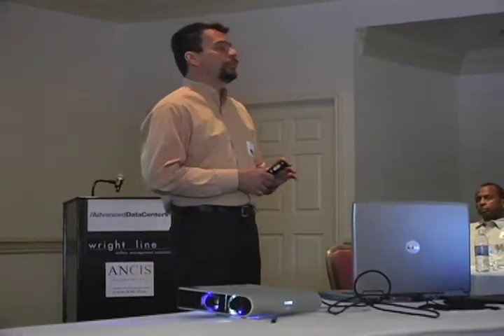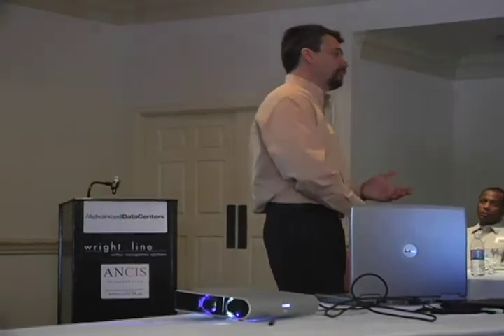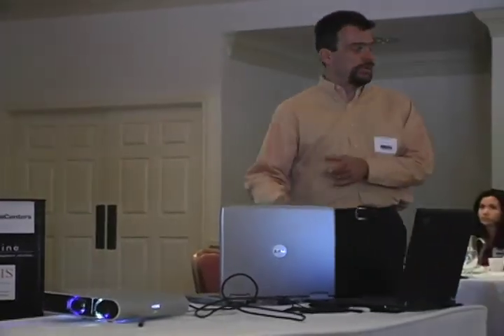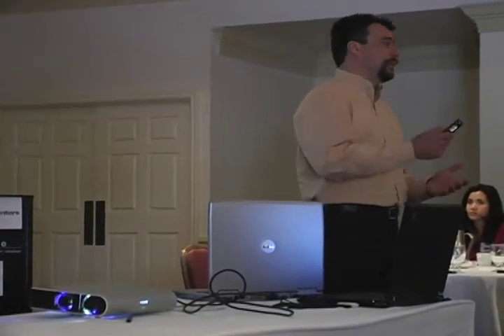How long is it? We can look at a bunch of different ROIs, but even in a legacy environment where you're connecting a containment system up to legacy racks, your ROI is based on the amount of reduction in fan energy. We saw in the ADC model that fan energy is significantly reduced, and that's really where the ROI comes from—less fan energy.